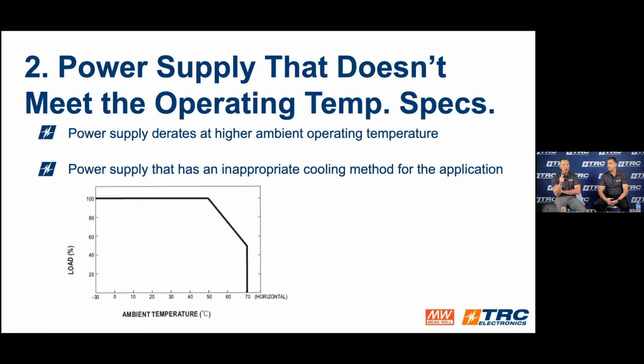Maybe Mike, you could talk about this too. Yeah, this is typical where you may have a system rated for 50 degrees C, but what about the ambient conditions inside the system? That system has heat generating components including the power supply, and the power supply's ambient may be different than the overall system ambient, so it's going to typically be a little hotter. That's why it's so important to run the temperature specs and actually predict what the temperature is going to be.